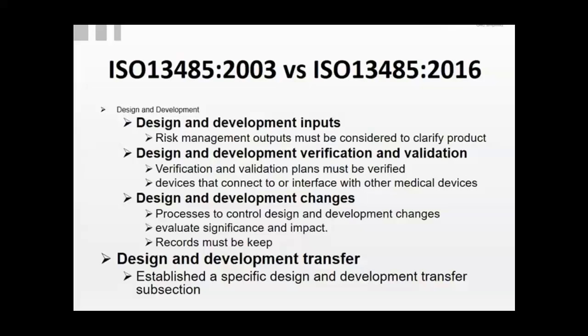Design and development verification validation. So one of the changes there is verification validation plans must be verified. Before, you just had the plans. Now you guys say, okay, these plans actually meet what we're talking about. So you have to actually verify the verification plan. Sounds redundant? Maybe. But more importantly, you can't just put a plan together and say, okay, let's agree to this plan because it's easy, we can do it real fast and we can get the equipment running. Now you have to justify why you did those plans. It can't just be something basic and simple. You have to actually put some thought into it and document and record those thoughts.